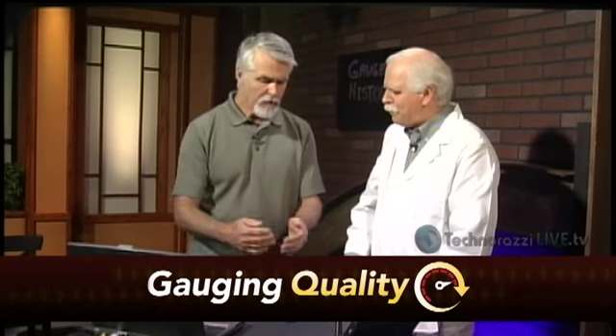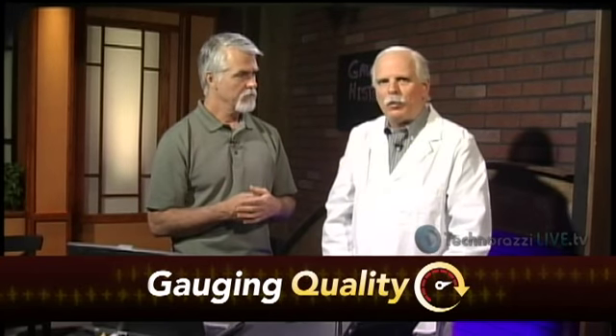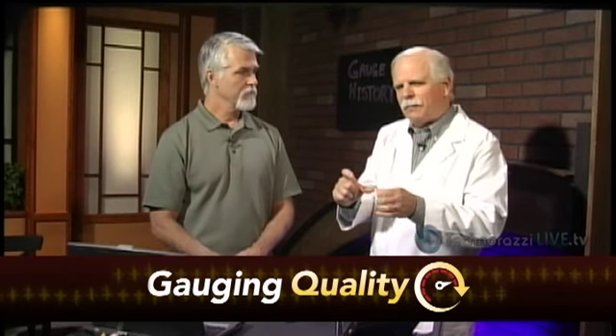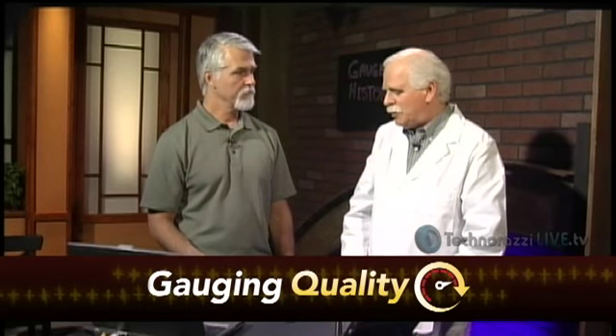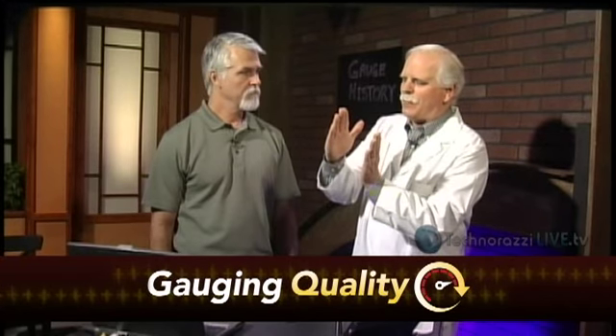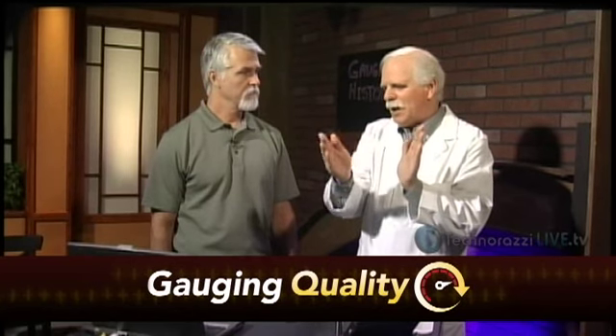And why would an anvil lose its flatness or parallelism? Wear in use. A great example would be anyone who measures anything ceramic. It wears them, and if you're using it just on the tip, you can't really get into the full feature, you can nick the edge, and you're going to wear the edges. And that won't show up using just one optical parallel. It may happen to be off parallel just in the perfect storm. Well, the second parallel is opened up some, so it's going to put it in a different orientation. That's where you have to use the two and it shows up.